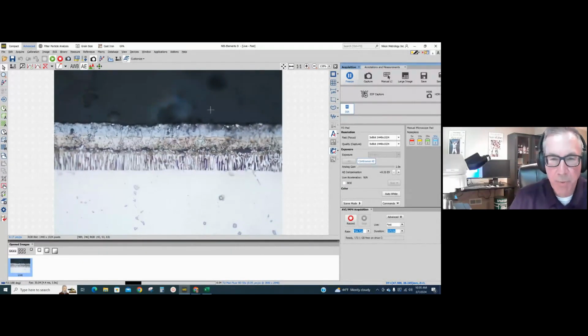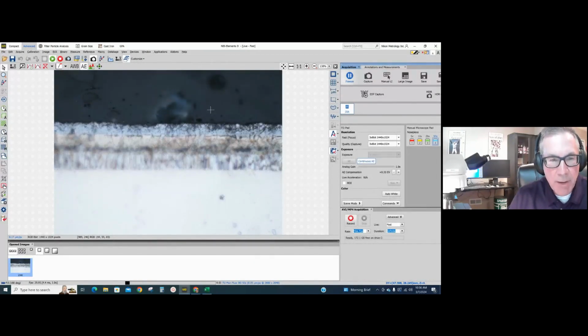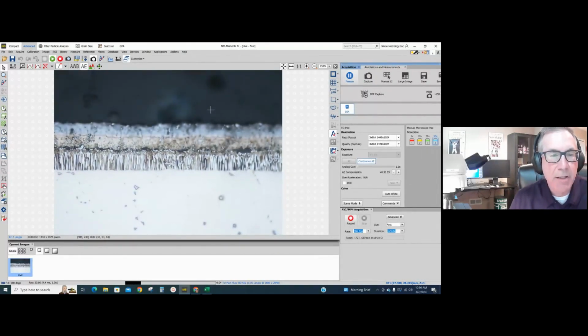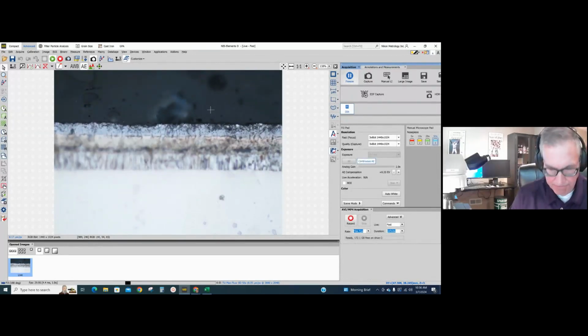But back to what I want to show you. We have an image at this higher magnification. The depth of focus is much smaller at the higher mag. You can see as I move my manual focus up and down, there's some parts of the image that are in focus and some parts that aren't. So we have this module called EDF, and it's going to show up under the applications. We can do this automatically with a motorized Z drive, but I'm going to show you the manual method. In the manual method, I essentially just start at one end of the focus and hit start.